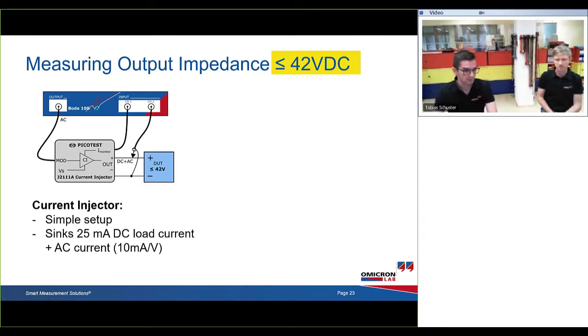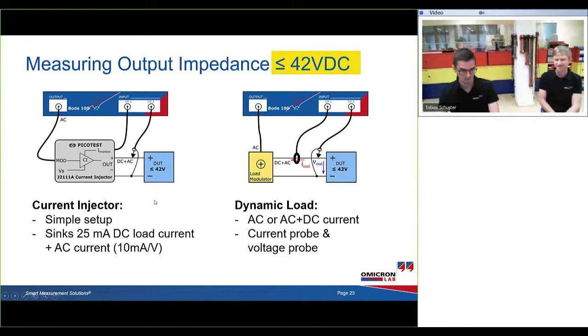Nice to know is that the current injector draws a DC current of 25 milliamps plus additionally an AC current which is 10 milliamps per volt. You can also use a dynamic load. You draw AC current or AC and DC current depending on the dynamic load that you have. There you need a current probe as well as a voltage probe to get the impedance.